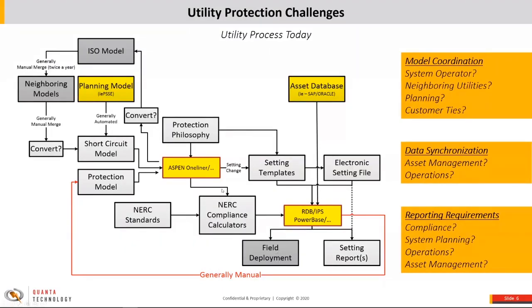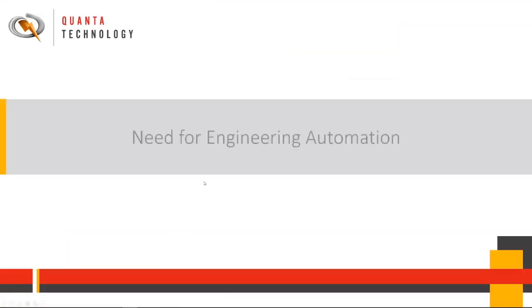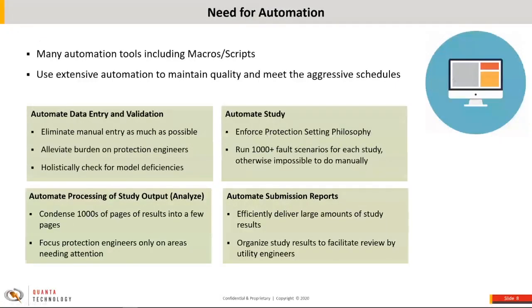This allows protection engineers to use their philosophies and setting templates to come up with setting changes and create electronic native setting files issued to the field through asset repositories. You'll also have NERC compliance challenges utilizing all these different data sources. Programs such as one-liner and Aspen RDB are really in the thick of all these activities that the protection engineer may do day-to-day, and therefore there's a great need for additional automation and API to reduce these efforts.